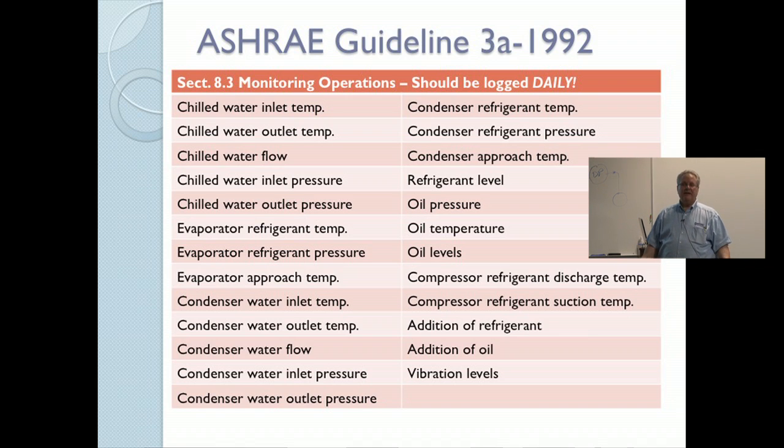Hopefully they give you some kind of alarm to tell you you ought to check something out, and hopefully you check it out. But nonetheless, they're going to stay running and lope along at that 70% because they can't go fully loaded. Well, guess what? If you're not doing your daily logs and catching these things, what's going to happen? You're going to have the 100-degree day, and you're going to need a 100% chiller, and you're not going to get it. And now it's an emergency call.